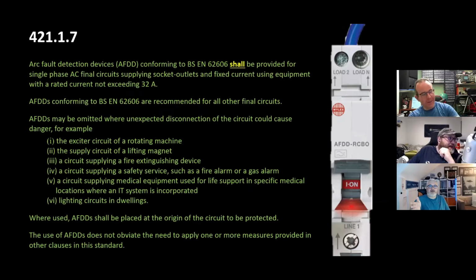This list is from protection against fault current, where there's exemptions for safety reasons. There's a list in there about reasons for safety why you may want to omit protection against overload current. Why would we not want it to turn off?